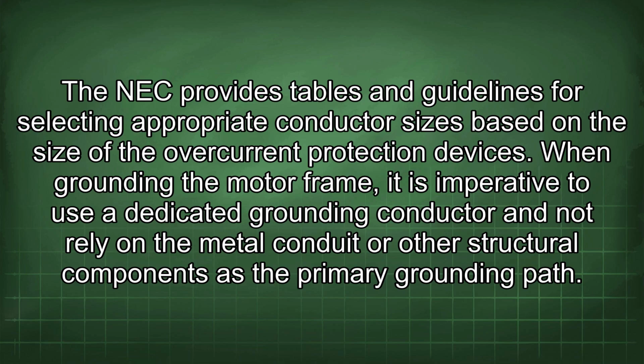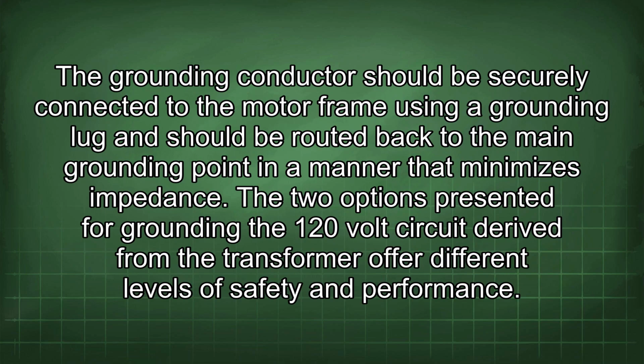When grounding the motor frame, it is imperative to use a dedicated grounding conductor and not rely on the metal conduit or other structural components as the primary grounding path. The grounding conductor should be securely connected to the motor frame using a grounding lug and should be routed back to the main grounding point in a manner that minimizes impedance.